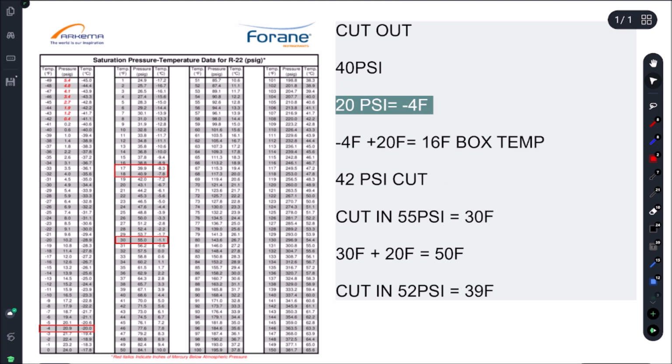Because if I lose all the refrigerant in this system and I can't get out there for 2 days, I do not want this thing running with no gas in the system. And then basically our compressor's running in a vacuum and just sucking in air. And then that turns into non-condensables, even though there's no gas in the system, but we have contamination in the system. So that's how I would set up this pressure switch as a safety only. Okay, so hopefully they do approve this because it'll be a nice service call to show how to set up an A421 and install it in this type of cabinet.